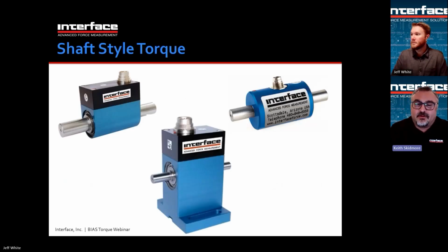These are some examples of shaft-style torque sensors. You can see on the left is a floating design intended to be attached by its shaft ends to the drive line and not mounted on a plate or anything underneath it. In the middle, we have a pedestal mount sensor, which is designed for the housing to be mounted on a plate. And then on the right is actually a reaction type sensor, shaft style. It may look like a rotating sensor, but in fact, that housing is attached on one end to the shaft. So it's just a rotary shaft sensor with a housing attached to it without any bearings or anything. So this one cannot spin, whereas the one on the left has bearings and can spin within its shaft.